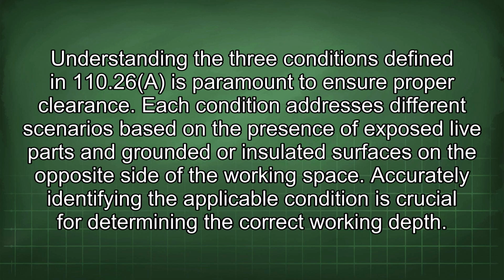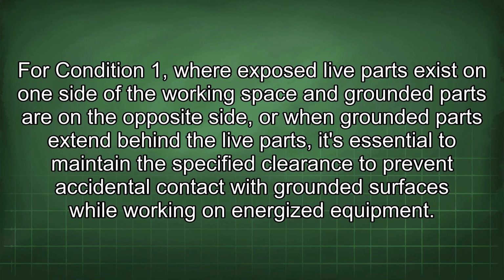Understanding the three conditions defined in 110.26 is paramount to ensure proper clearance. Each condition addresses different scenarios based on the presence of exposed live parts and grounded or insulated surfaces on the opposite side of the working space. Accurately identifying the applicable condition is crucial for determining the correct working depth. For Condition 1, where exposed live parts exist on one side of the working space and grounded parts are on the opposite side, or when grounded parts extend behind the live parts, it's essential to maintain the specified clearance to prevent accidental contact with grounded surfaces while working on energized equipment.